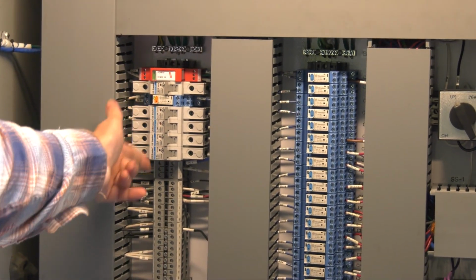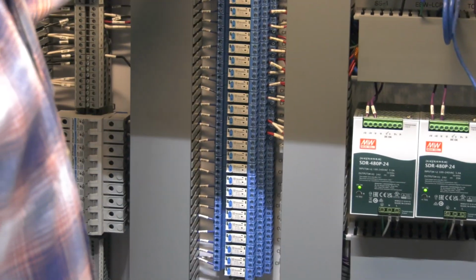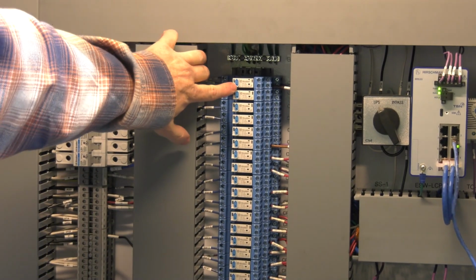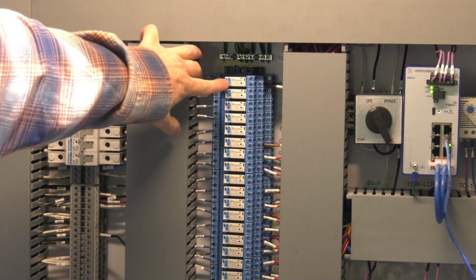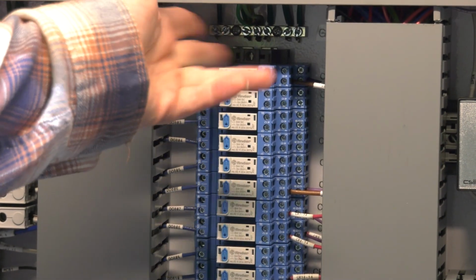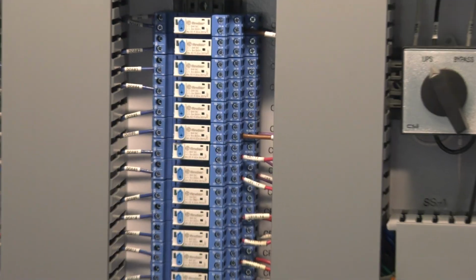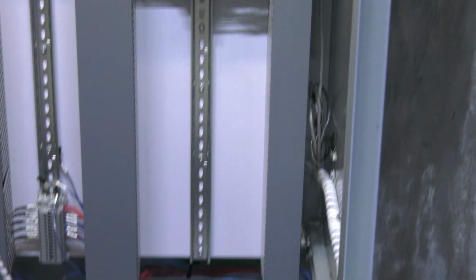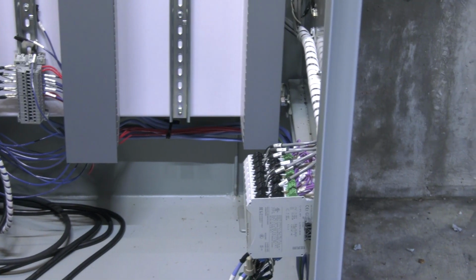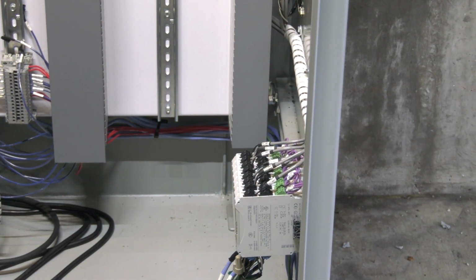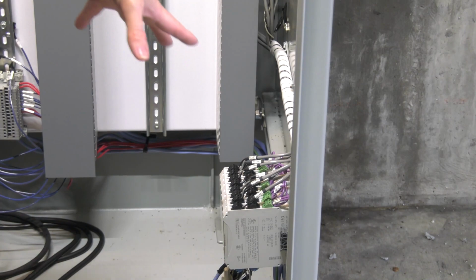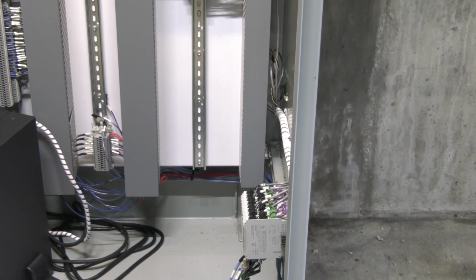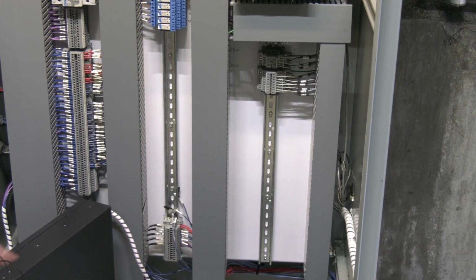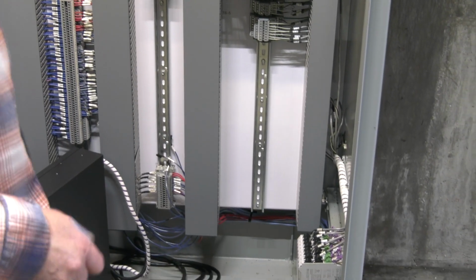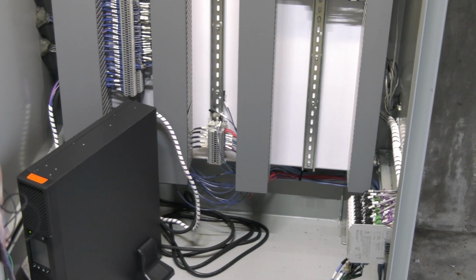Let's see, circuit breakers, relays. You can force the relay on temporarily by pressing the blue button, or you can turn that flag and that'll force that relay on. Down here you've got your intrinsic safety barriers. If you need to replace those for any reason, just the terminals pop off and you can replace the ISB. There's no setup configuration, no dip switches, just replace it. And that's pretty much it.